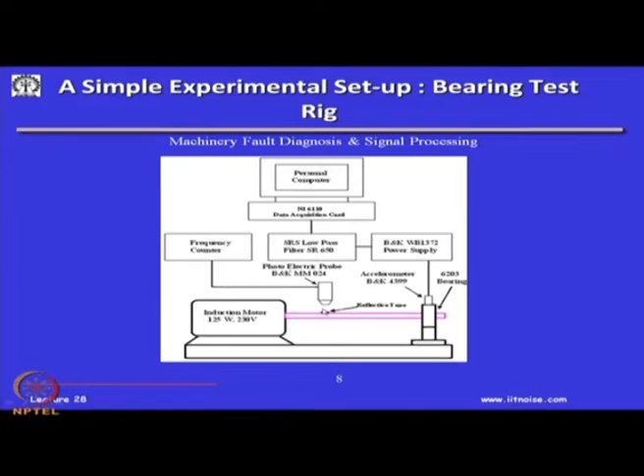Okay. So, to understand this, we did a small experiment in the lab, and basically what we have here is a motor driving a 6203 bearing. All we have to do is put an accelerometer and a filter, have an NI data acquisition card, and we take all the data to the computer, and then we have a photoelectric probe to measure the rotational speed, because as you will see, all the bearing frequencies are dependent on the rotational speed of this shaft, and these frequencies can actually be calculated.